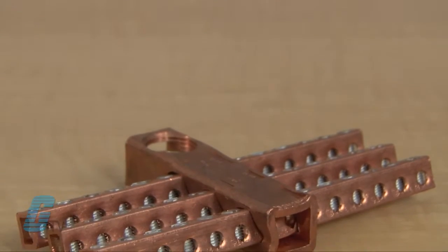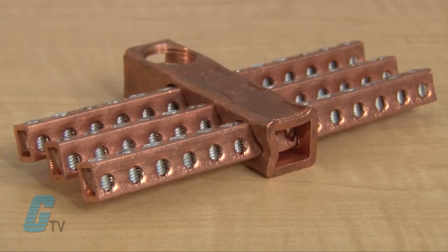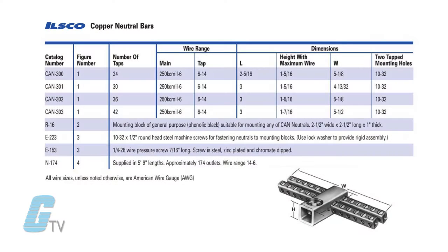The compact design allows for up to 42 circuit taps that can be made within the 5.5 inches of space provided. A wide range of conductor sizes can be used in the same connector, with tap range from 6 gauge to 14 gauge wire and the main from 250 MCM to 6 gauge wire in the standard CAN series.